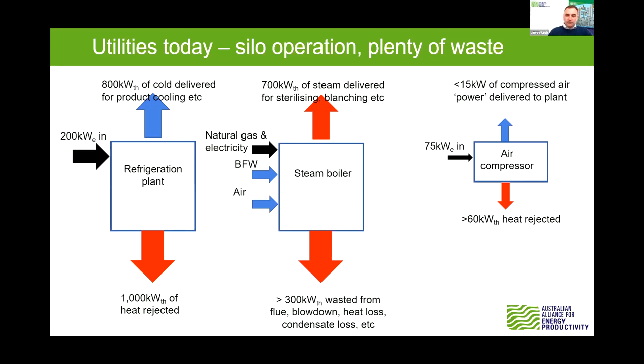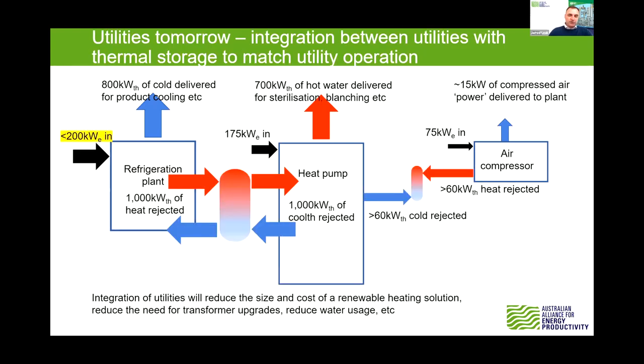So going forward, here is one such opportunity that we'll be exploring some solutions for today. And that is looking at, instead of operating utilities in a silo, having them integrated between them. Here's one such way to do that, with something of a thermal battery sitting in between a refrigeration plant and a heat pump, where they could potentially balance out, where the heat coming from the refrigeration plant is used by a heat pump, improving the coefficient of performance, reducing the size, reducing electrical load, yet still being able to deliver the heating that's needed for the plant.